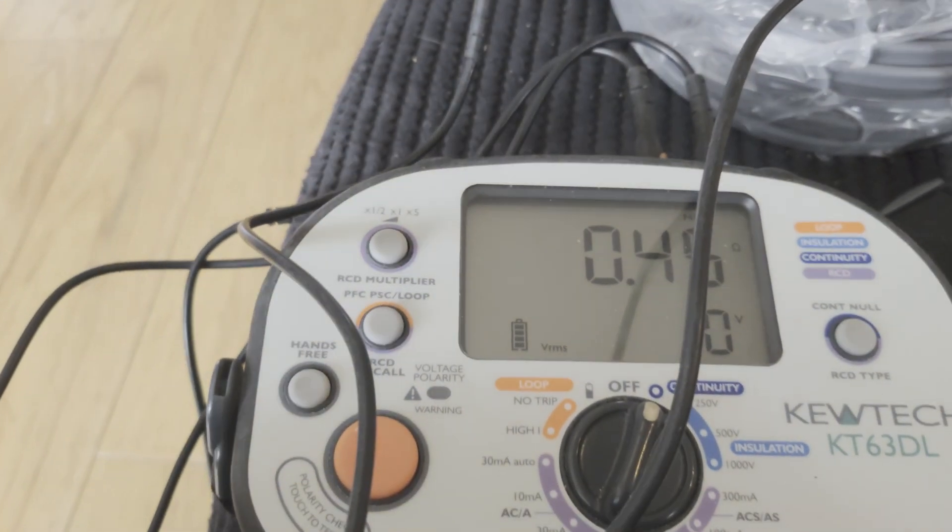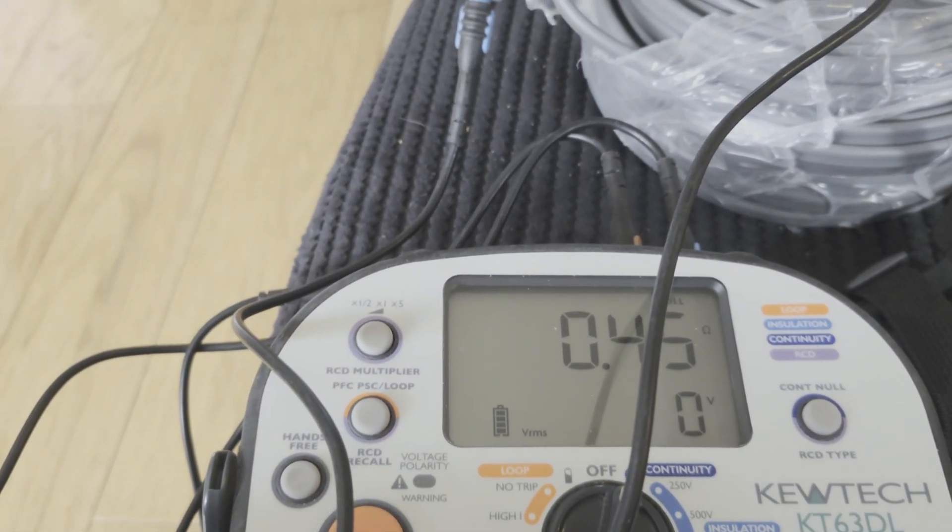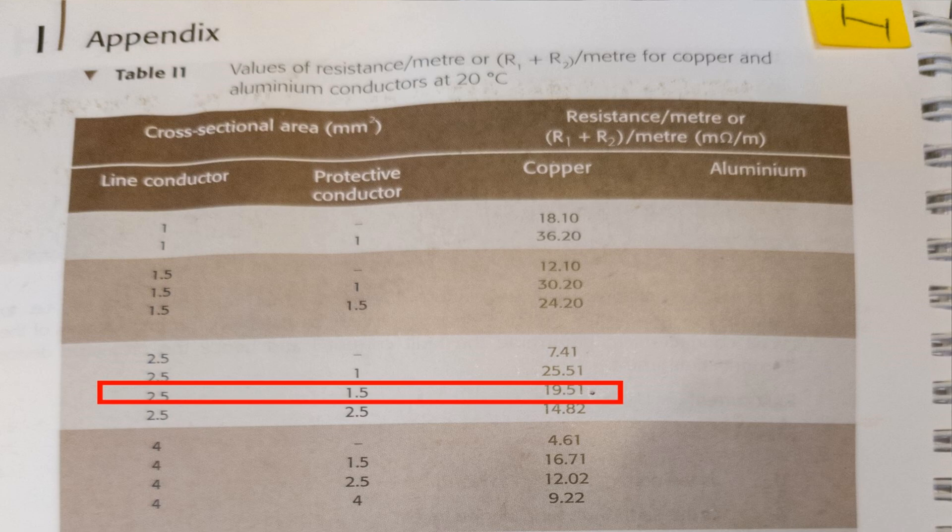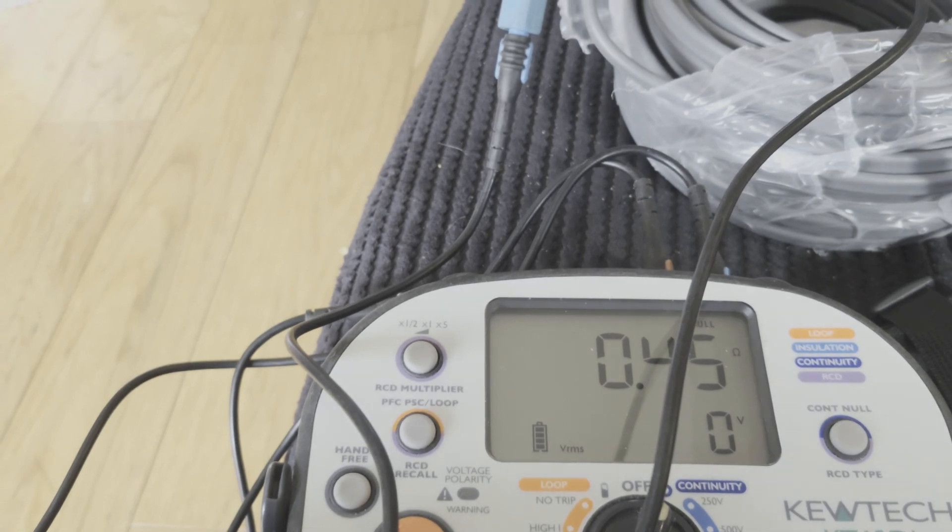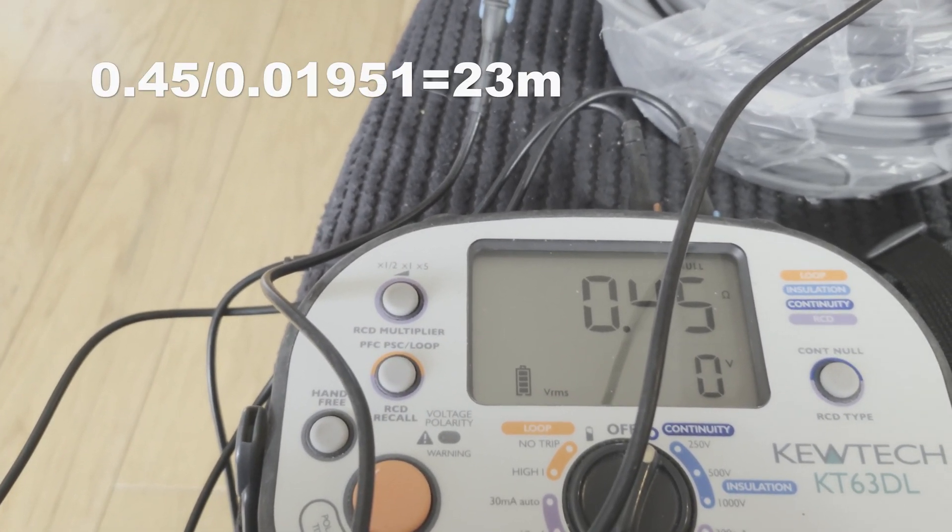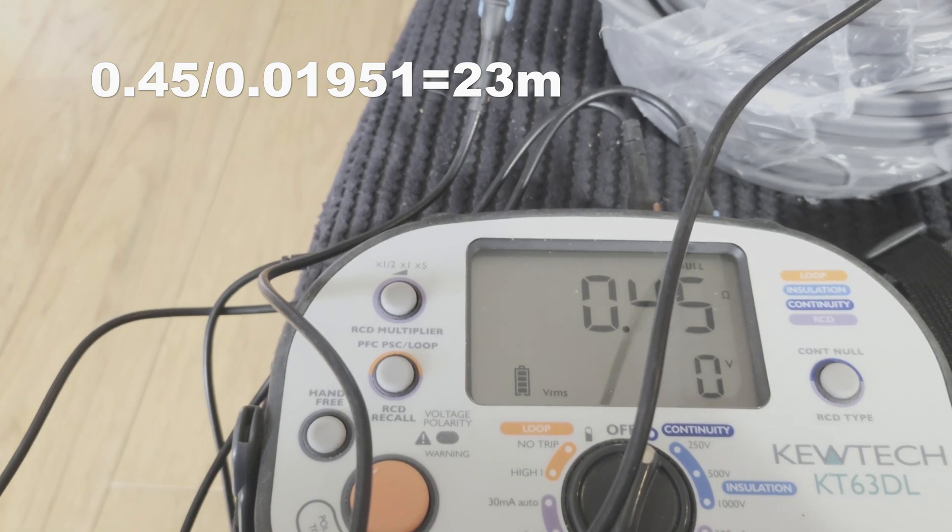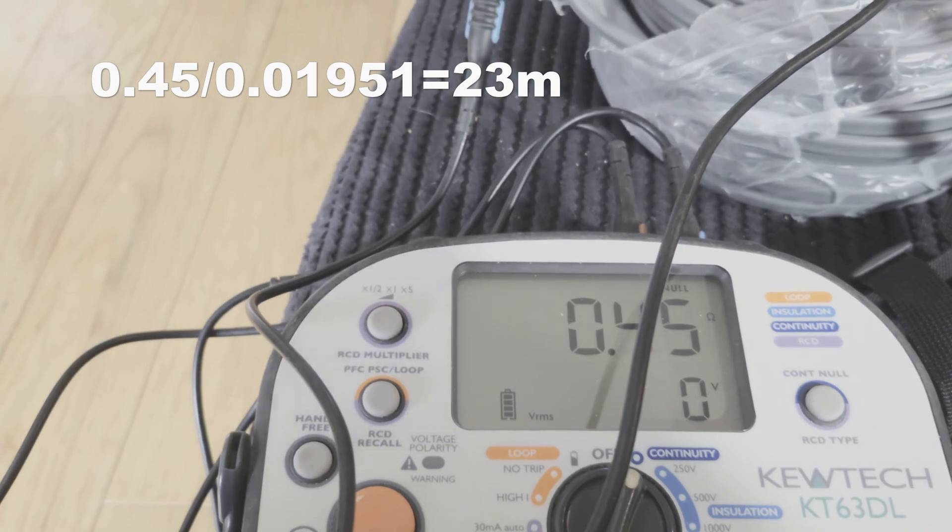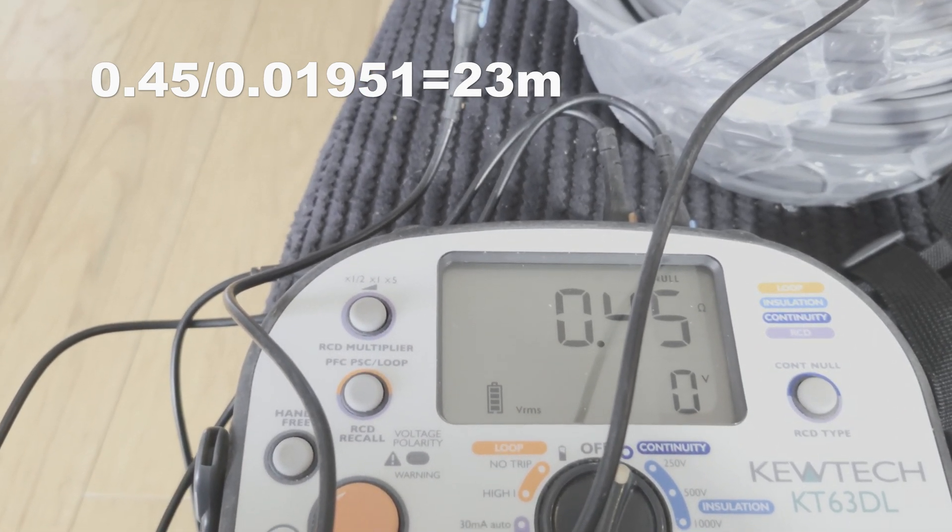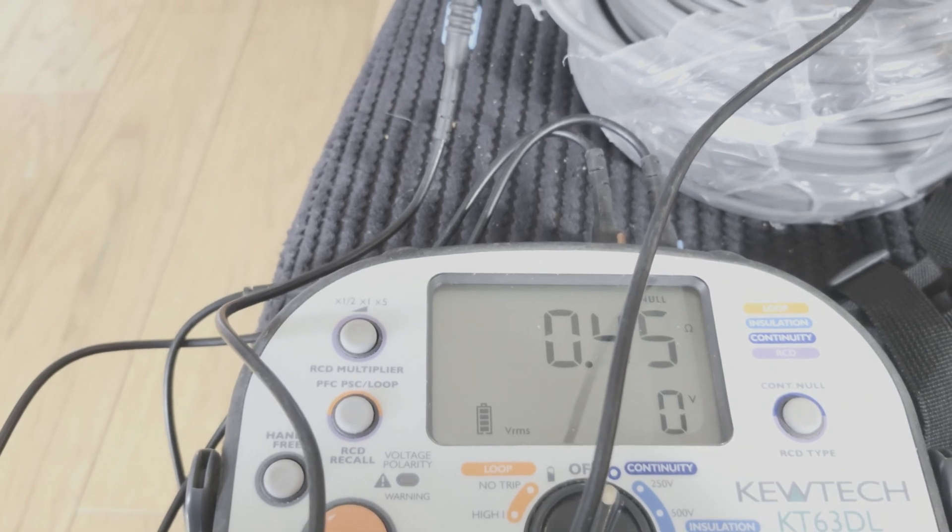So how do I know that's right? Well in the on-site guide table I1, it will give you the resistance values you can use to work out if that value is actually right for the cable length that you're going to be using. So put it up on the screen. As you can see, I need to divide that value by 0.01951. If I do that, you will see on the screen the value that comes to, which is near enough 23 meters, which is exactly right. So that 0.45 is exactly the reading I should be getting from those cables.